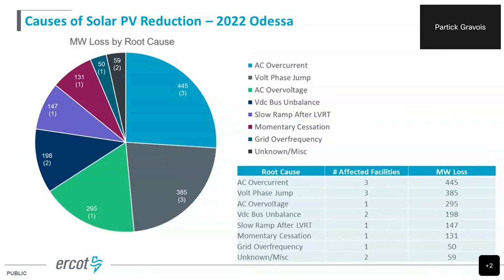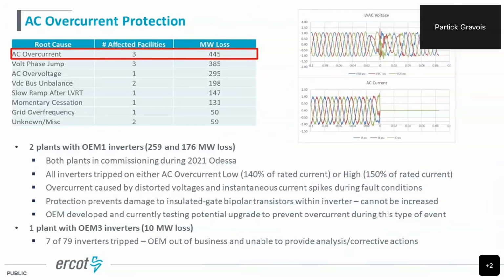So again, we'll go through these one by one. Overcurrent. We had 3 facilities lose a combined 445 megawatts. On the top, you're seeing a distorted voltage waveform. This is at the inverter level. You see this phase shift can cause a spike in the current. This is something we saw in 2 facilities that had all their inverters trip off. Both of these plants were not involved in 2021. They were still being commissioned.